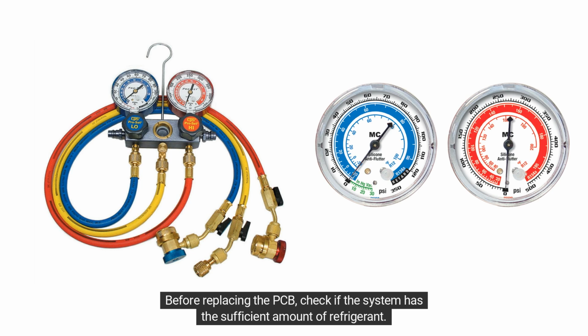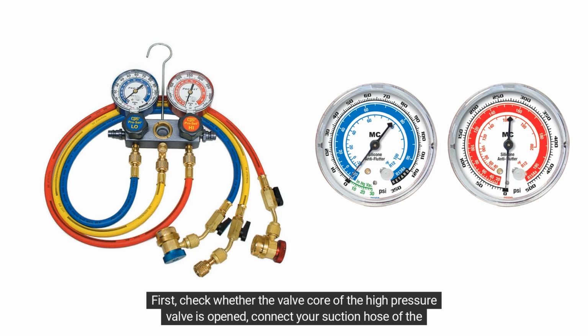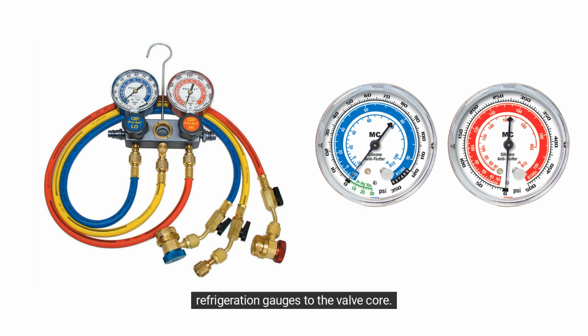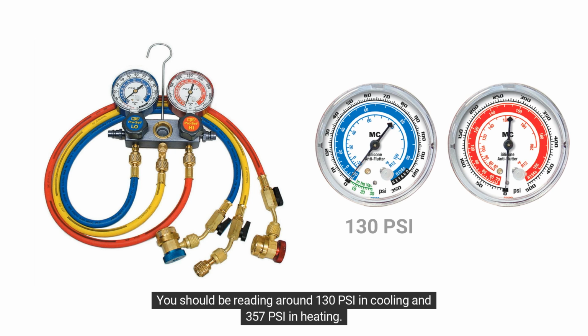Before replacing the PCB, check if the system has the sufficient amount of refrigerant. First, check whether the valve core of the high-pressure valve is open. Connect your suction hose of the refrigeration gauges to the valve core. You should be reading around 130 psi in cooling and 357 psi in heating.